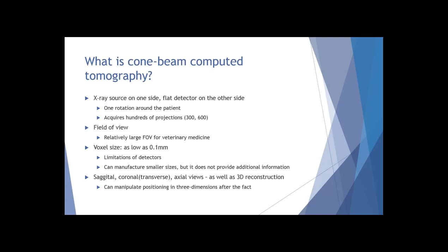We look at voxel size, which in a very simplistic way is essentially a pixel in 3D. Voxel size is something manufacturers throw out as a selling point. You can go into smaller sizes, but as you cut that cube into more and more pieces, it doesn't necessarily provide additional information - so that's just something to know and keep in mind.